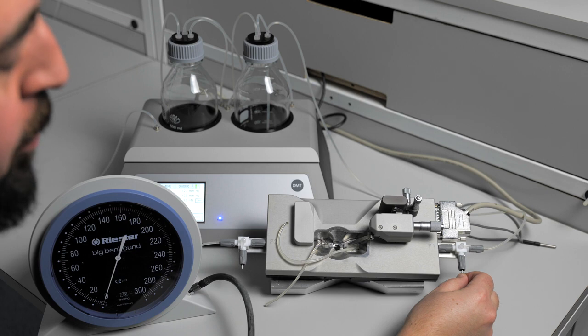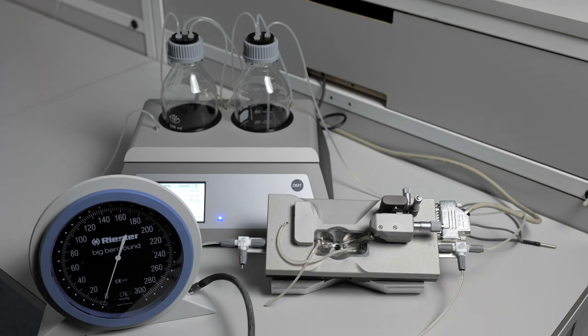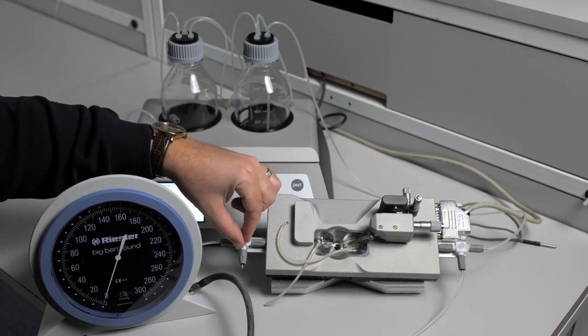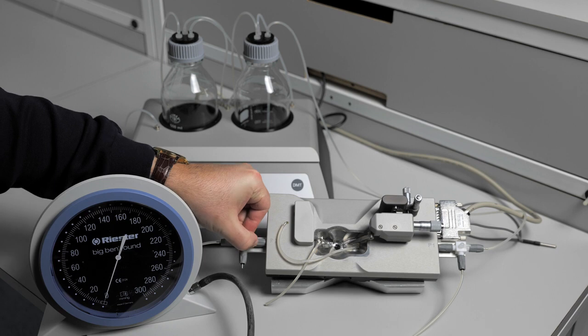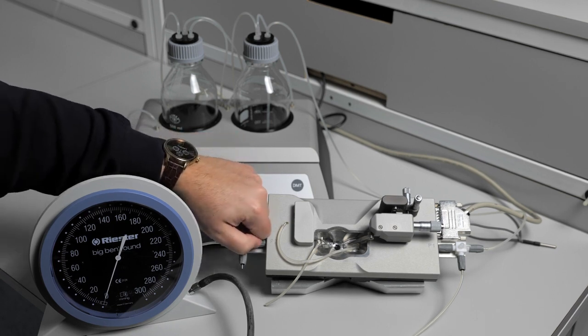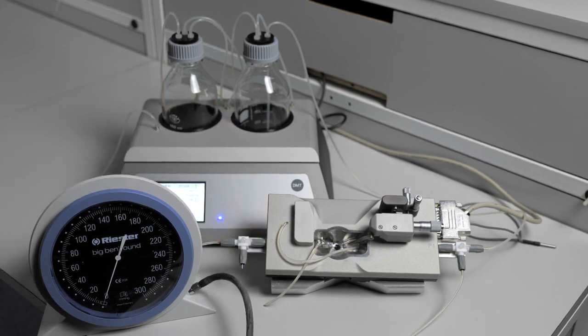Place the big Ben manometer on the open port of your P1 three-way valve. Make sure that it is open to the chamber and close the P2 three-way valve to the chamber. Add pressure, but do not go over 200 millimeters of mercury. It should be holding perfectly steady. If there is any drop at all, you know you have a pressure leak in the chamber.